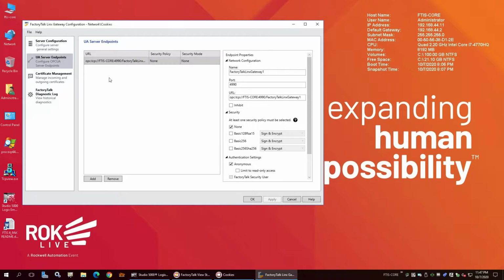And if we come down to UA server endpoints, we see similar configuration options for OPC UA as we saw in Kepware and the Windows version of Kepware, as well as what we're going to see in the Linux version, despite the look and feel being different. So this has an application name, FactoryTalk Linx Gateway, which is going to show up in the URL or the URI.